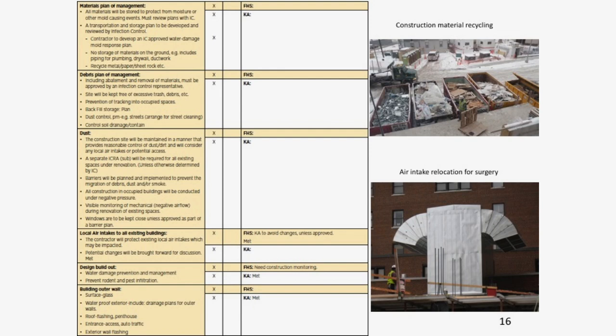You may be wondering on slide 16 what that big old thing is that's hanging over the top. That was actually moving the air intake for our operating rooms up and away from some hot work and from jackhammering and a number of other things below it. It got it away so that the fumes and the dust wouldn't get into the fan system and create odor problems, and that really can mess up surgery if the surgeon can't concentrate, and we want them to concentrate while doing some delicate surgery because it stinks.